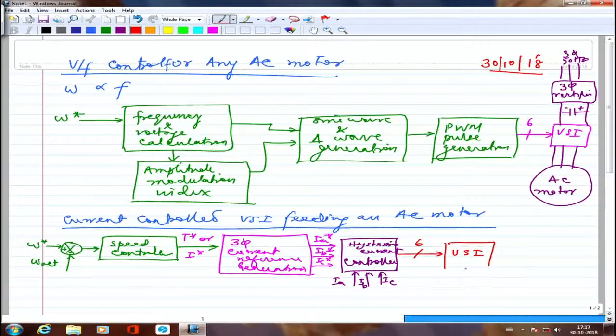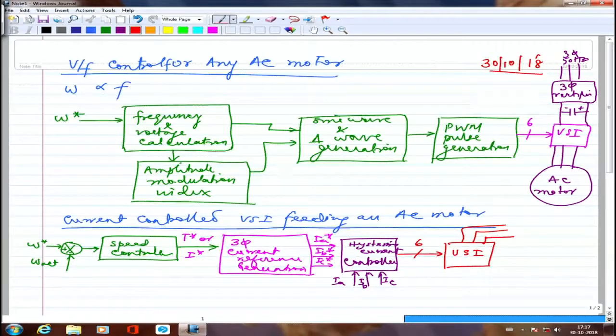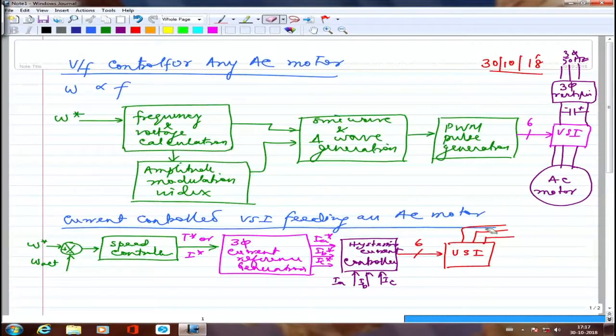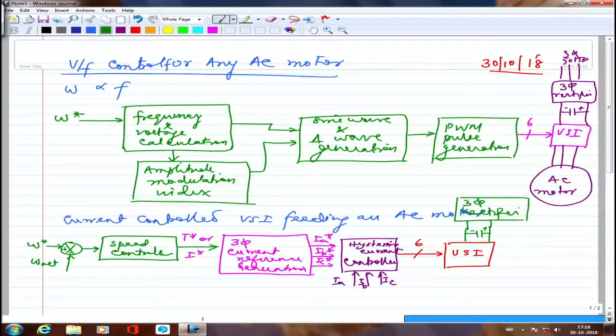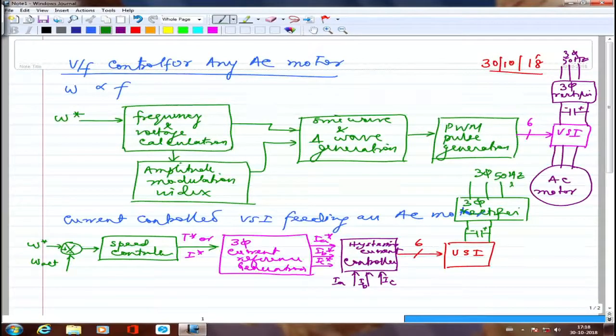On the power side: DC bus with electrolytic capacitor (plus, minus), a 3-phase rectifier — for a large capacity drive I take 3-phase input, for small capacity single phase. The 3-phase 50 Hz input is rectified and filtered, and the VSI output goes to the AC motor. I sense the three-phase currents using current transformers or other sensors — the high currents (tens or hundreds of amperes) must be stepped down since electronic circuits handle only milliamperes.